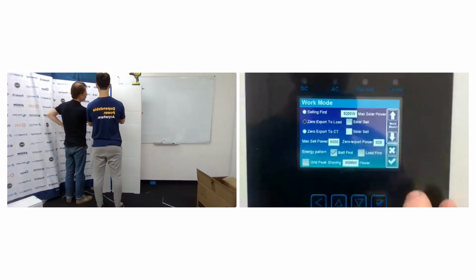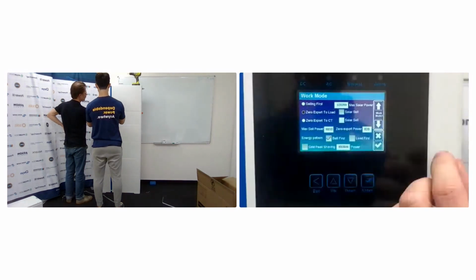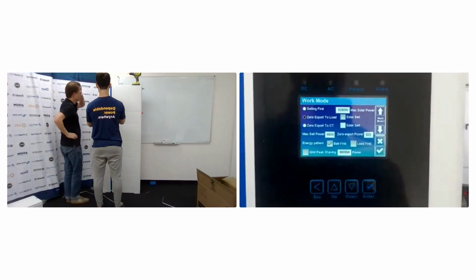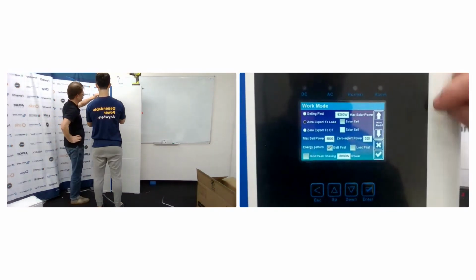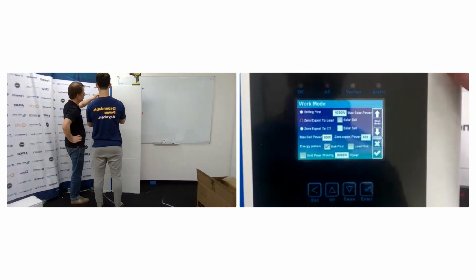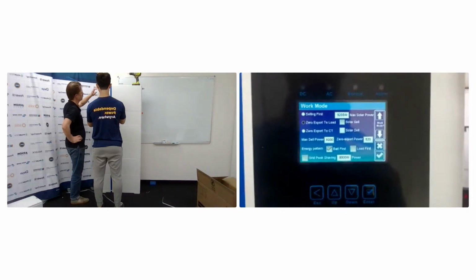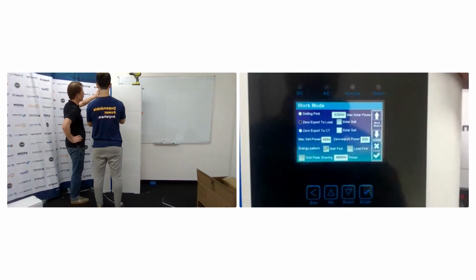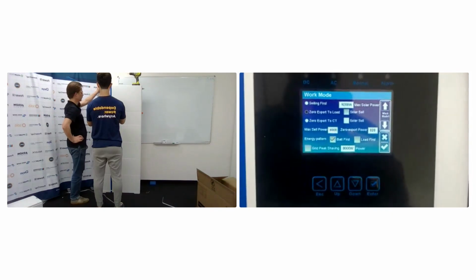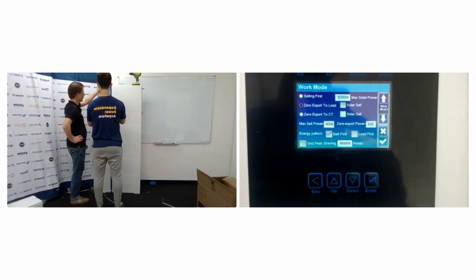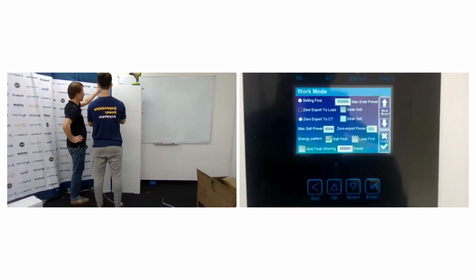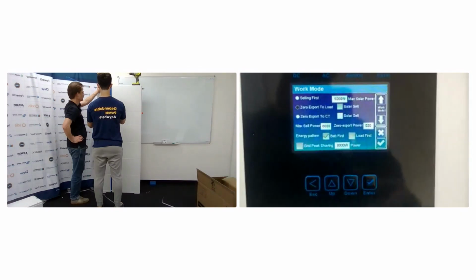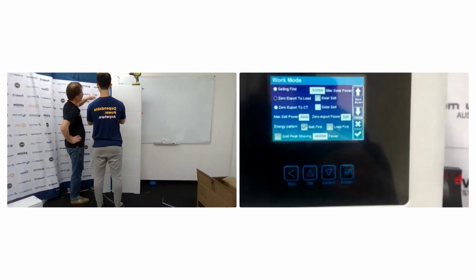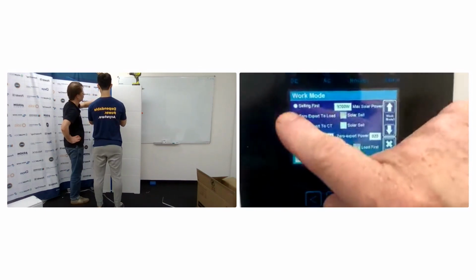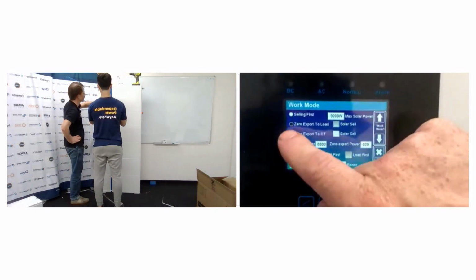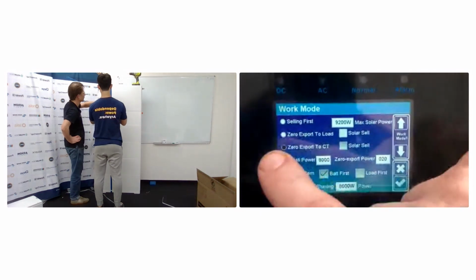Yeah, the menu is identical to the other one. The system work mode, this is where you want to set it up for how you're going to use the grid, because if it's a grid tie setup, you don't want it just using power, whatever power is available from the grid whenever it can. Unlike an off-grid setup, when the generator's on, you're usually just using as much power from it as you can. So this is where you control that. There's a few different modes, but most of the time you're going to be doing 0 export to CT.